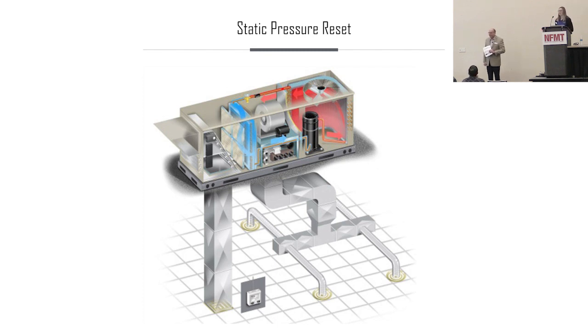So even when you think there may not be an option to save some money, there may be a way. It may be small, but honestly, anything small is money saved, in my opinion. And to be clear, the manufacturer signed off on it. They just had not envisioned that particular use case. You're right, the compressors are locked out. I guess there's no reason you can't ramp the fan down to a minimum. They just had not considered that use case in the design of their package unit.